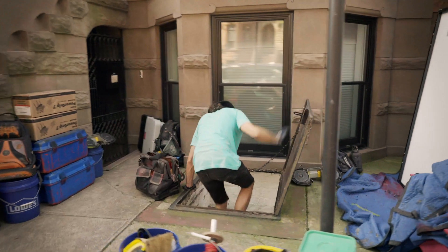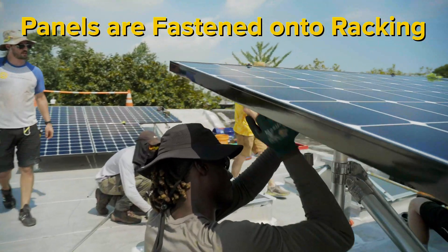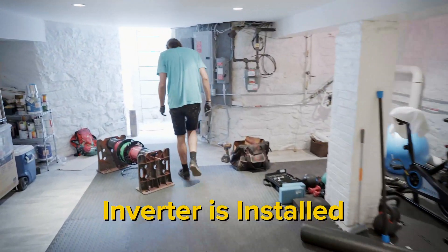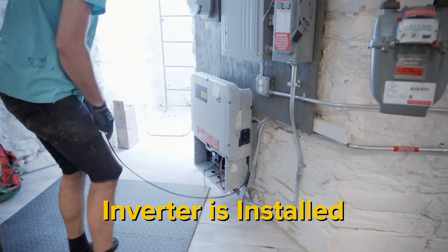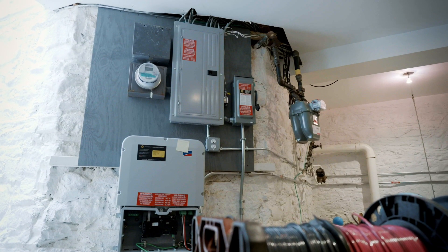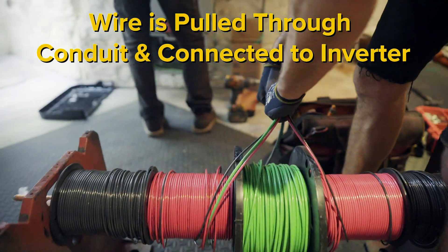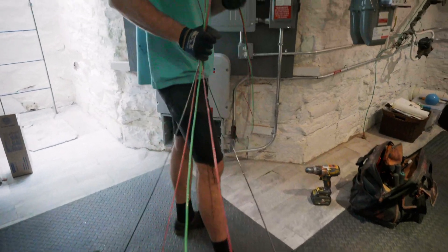We then enter into the building basement either in the front of the building or backyard. Solar panels are mechanically fastened to the heavy-duty solar racking. The inverter, or brains of your solar system, is installed either on the roof or in the basement near your electrical service panel. The inverter is approximately 20 by 30 by 8 inches, or the size of a carry-on bag. We pull the wire through the conduit to the basement, then connect all the DC and AC wiring to the inverter.